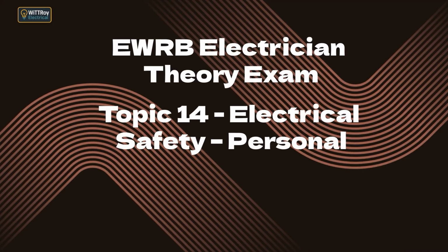14.2b Explain the safety tag system. A safety tag is a warning device placed at an isolator. It identifies who isolated the equipment, when, and why. It warns others not to operate the equipment. A tag alone does not prevent operation, it must be combined with lock-off whenever possible.